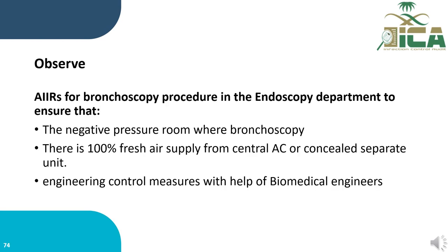For the observation, you need to observe the airborne infection isolation room for the bronchoscopy procedure in the endoscopy department to ensure that the negative pressure room where the bronchoscopy is performed fulfills the requirements of an airborne infection isolation room in order to prevent the risk associated with any aerosol generating procedure, and also to be sure that there is 100% fresh air supply from the central AC or a separate split unit.